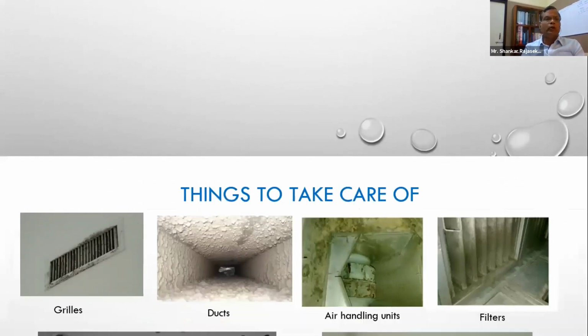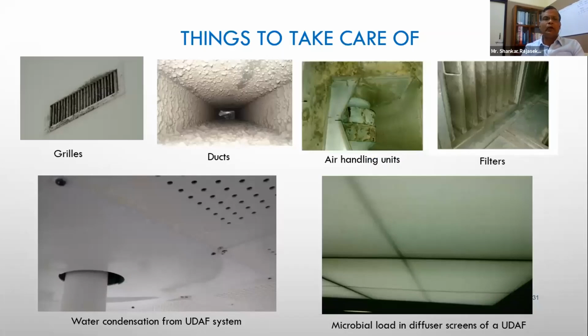Of course, we all know the grills, ducts, air handling units, filters, all these things need to be taken care of. There have been cases where, not because of some water pipeline getting ruptured or something like that, but because of problems in pressure differentials, air from above the false ceiling mixes with the operating room environment through the light pendant or the surgical pendant shafts. We have seen water condensation in several places.